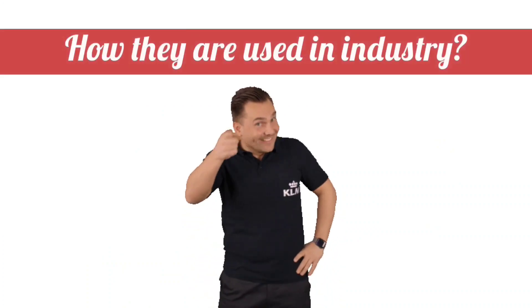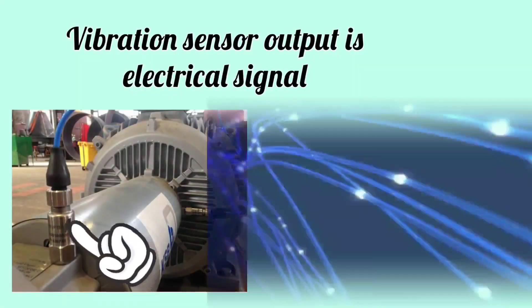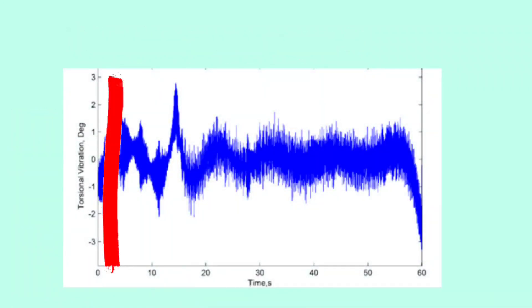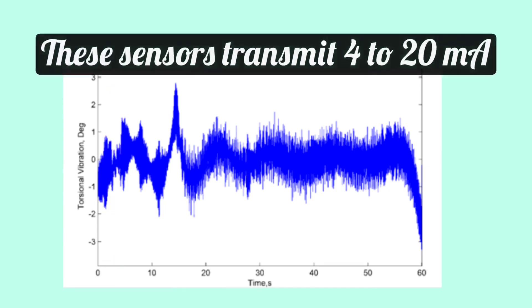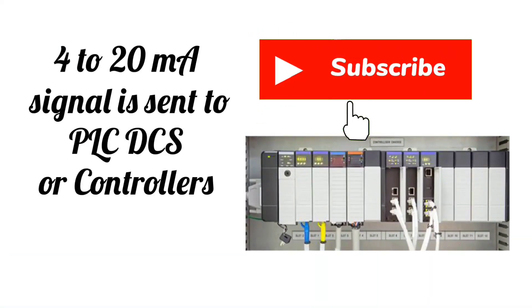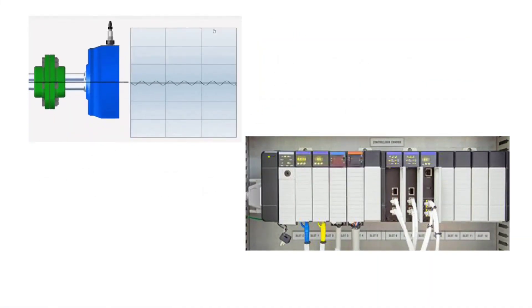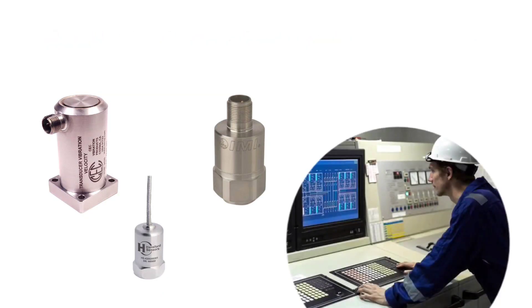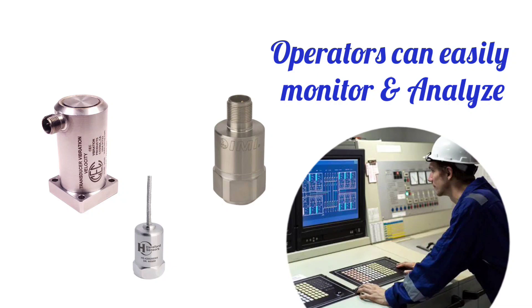How is this done? Vibration sensors output an electrical signal. According to the overall vibration level, these sensors transmit a 4 to 20 mA signal, which is sent to a PLC, DCS, or controller, which stops the machinery at high vibration levels and avoids machine failure. With the help of vibration sensors, operators can easily monitor and analyze the equipment.